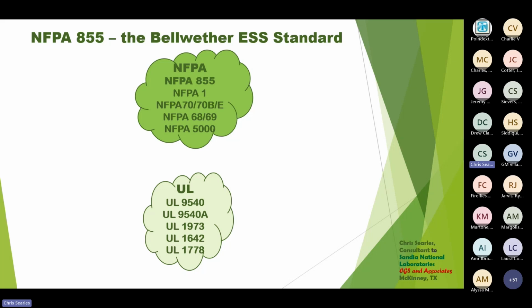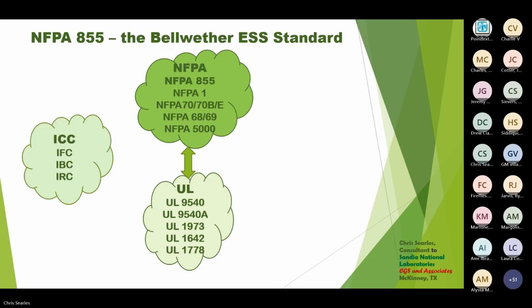UL 1973 has listing requirements for battery and BES components. It's considered a standby battery application standard, but has now enlarged to incorporate energy storage testing, and lead acid as well as lithium, sodium metal chloride, and other technologies must comply with testing requirements under 1973 that feed into 9540. 1642 is going through—it's the lithium cell standard—and it's now probably going to roll into 1973. UL 1778 is the UPS standard. Then we have the ICC, the three I codes that we talked about.